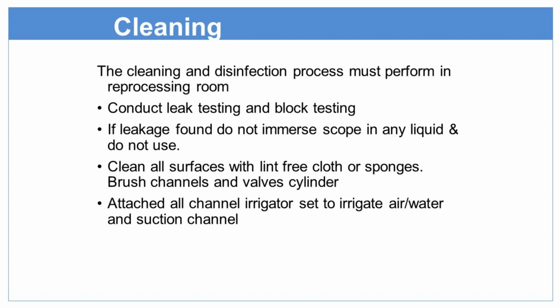Whenever we do any procedure in the procedure room, afterwards the used equipment or used endoscope we must wrap in some sheet and bring it to the dirty room, where the cleaning procedure or other mechanical procedure will be done. So in cleaning, conduct leak testing and block testing. If leakage is found, do not immerse the scope in any liquid and don't use it. Keep it separate so another person will not mistakenly prepare this device for another patient.